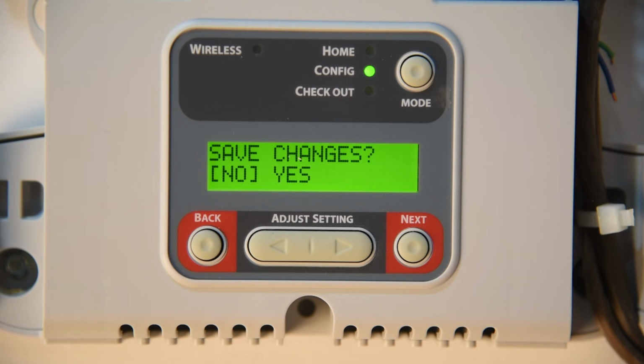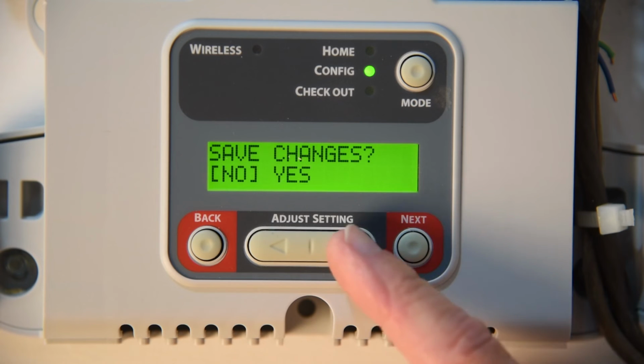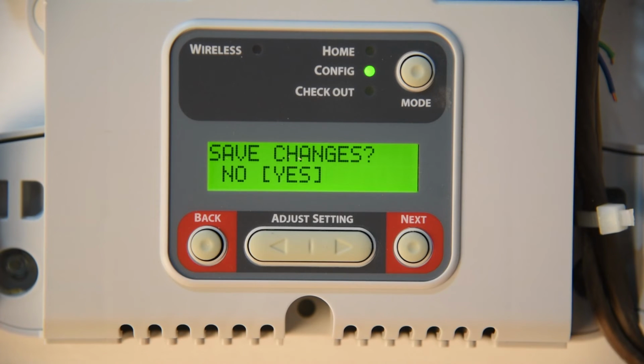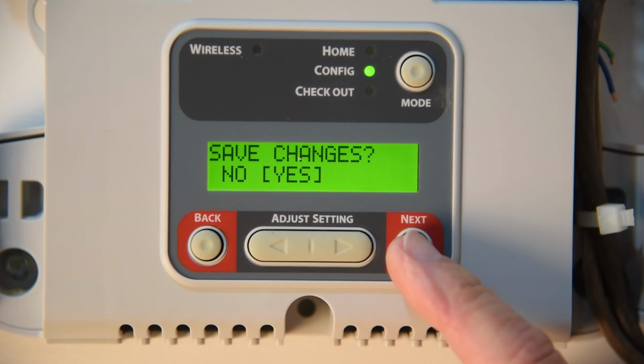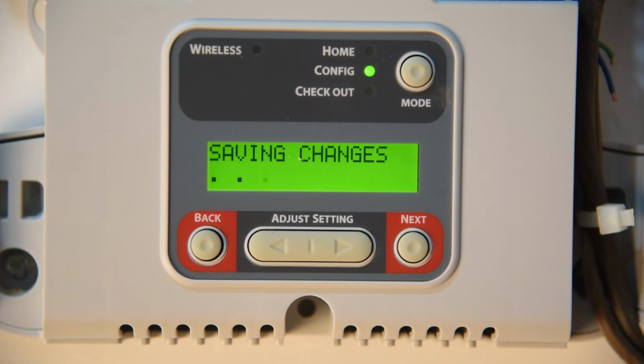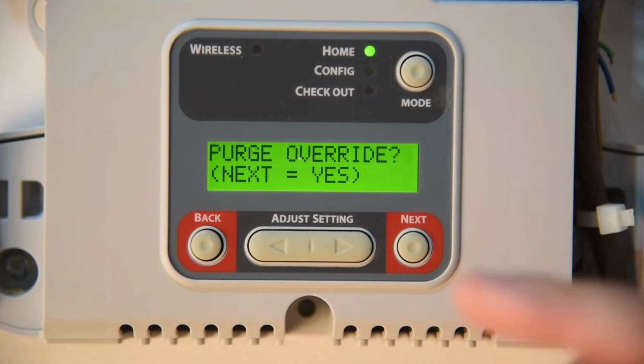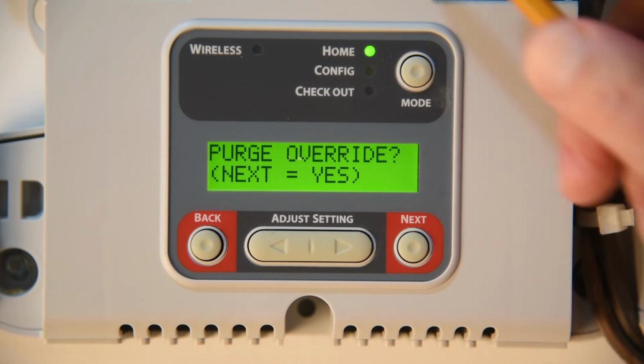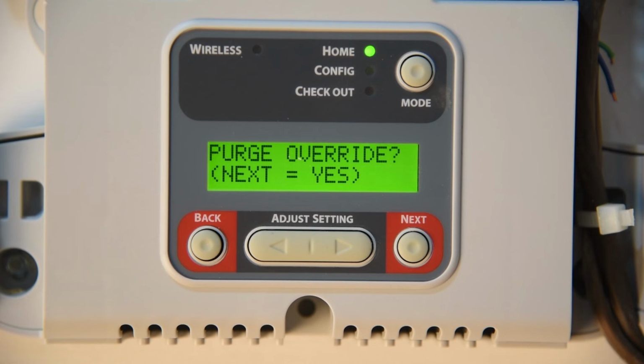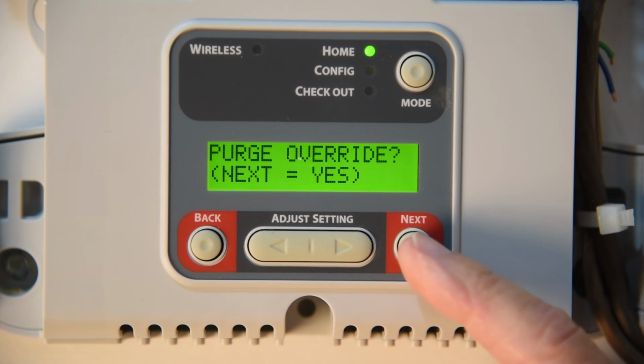Okay, then I'm offered the chance to save changes. Well, I've been bouncing around, so I better save them. So I'm going to say yes, and now it's saving the changes. Once it's saved, it will purge the system. You can say next. If you notice, the purge came on, the fan came on in zone 1 and 2. Well, really there's nothing in there to purge, so I'm going to say override yes.